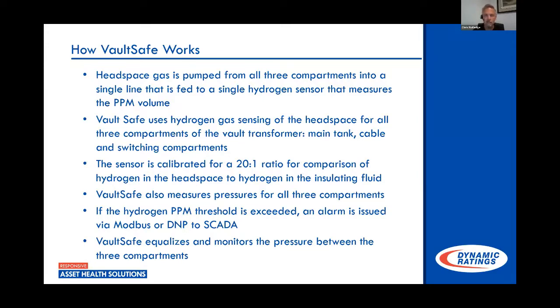And again, with these transformers being a secondary loop, there's no harm in getting them out of service. It doesn't affect your end customer. So when you get these alarms and you see that parts per million change, go on and take it out. Let's get it tested and let's find the problem. Because I think alarm response is a huge thing. Alarms that are ignored, why did you bother with the monitoring then? You do see from this side of the industry, and even when I was at the utility, there's a lot of difficulty in getting these online, but they really can save you in these kinds of cases, especially with a transformer like this, where it's really not that big a deal to get it out of service.